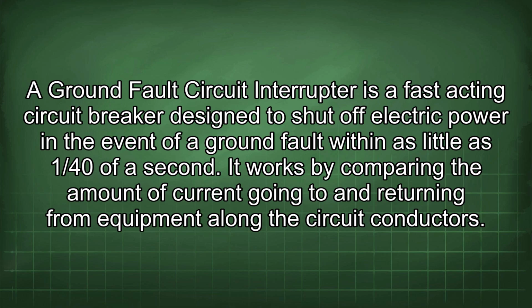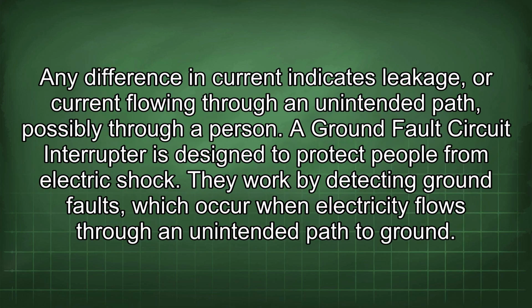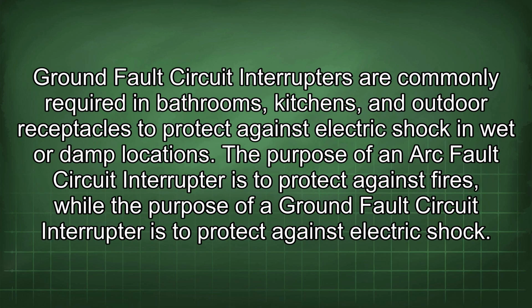A ground fault circuit interrupter is a fast-acting circuit breaker designed to shut off electric power in the event of a ground fault within as little as 1/40 of a second. It works by comparing the amount of current going to and returning from equipment along the circuit conductors. Any difference in current indicates leakage or current flowing through an unintended path, possibly through a person. A ground fault circuit interrupter is designed to protect people from electric shock. They work by detecting ground faults, which occur when electricity flows through an unintended path to ground. Ground fault circuit interrupters are commonly required in bathrooms, kitchens, and outdoor receptacles to protect against electric shock in wet or damp locations.